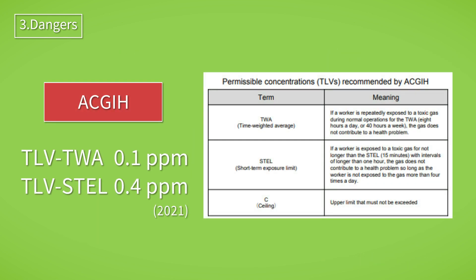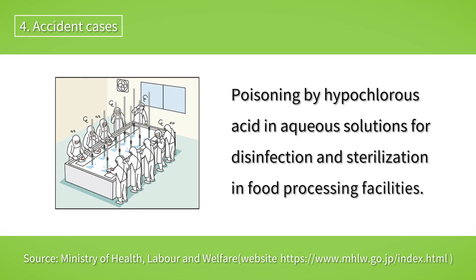Permissible concentrations are specified for gases harmful to the human body. In the case of chlorine, the TLV-TWA and TLV-STEL are specified at very low concentrations of 0.1 ppm and 0.4 ppm respectively.